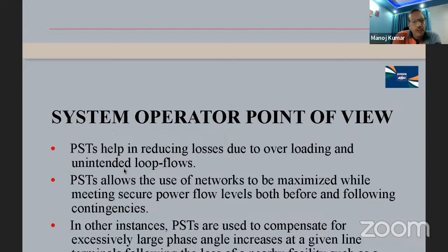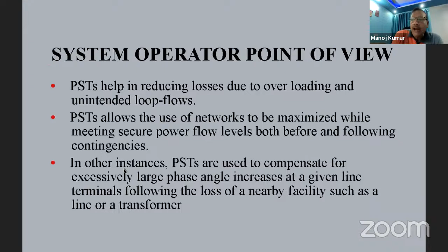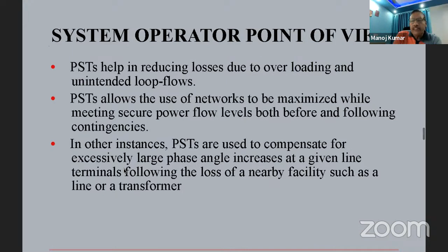This PST helps us in reducing the losses, because whenever there are overloaded lines, we can transfer power to the other loops. This transformer is effectively used to optimize the power flow in the transmission network, reduce the system losses, and control the active power flows in the network. This is one of the items BHEL has made and successfully tested.